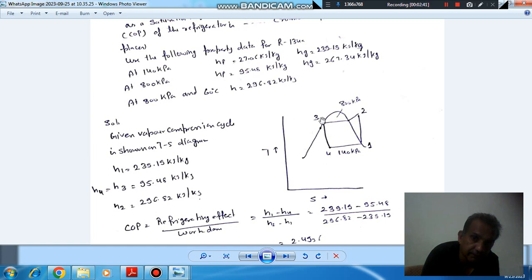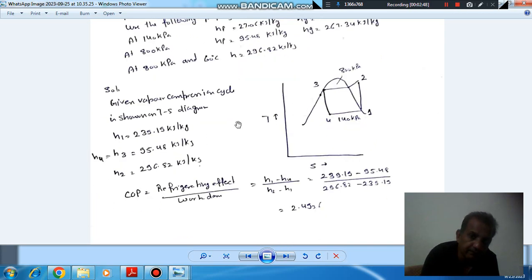At 800 kPa saturated liquid, hf = 95.48 kJ/kg per kg, which is h3 or h4. From the diagram, we can see the evaporation process. The refrigerating effect per kg is h1 minus h4. COP equals the refrigerating effect divided by work input: (h1 - h4) divided by (h2 - h1). With these values, you can find COP equals approximately 2.493.